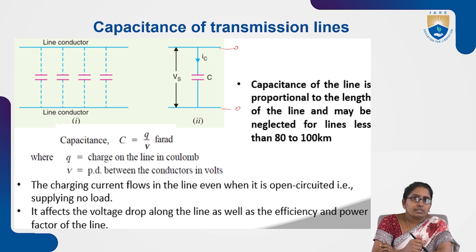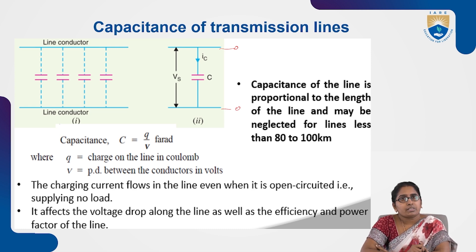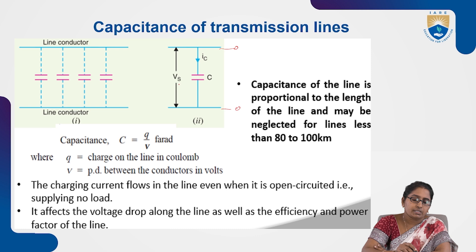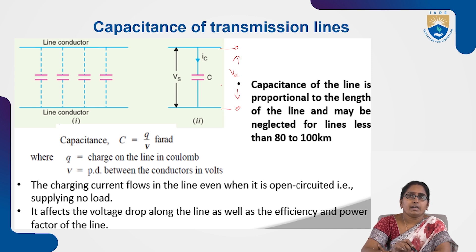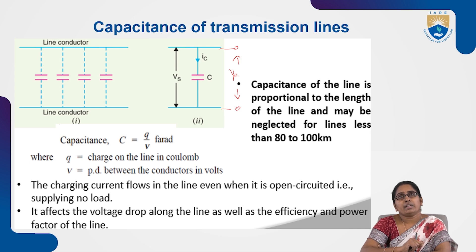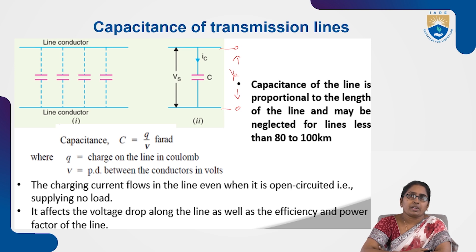Due to this charging current flowing because of the capacitance, there will be some voltage drop between the sending end voltage Vs and the receiving side. This will also affect the efficiency of the transmission line and the power factor of the line. This is how capacitance affects the performance of the transmission line.